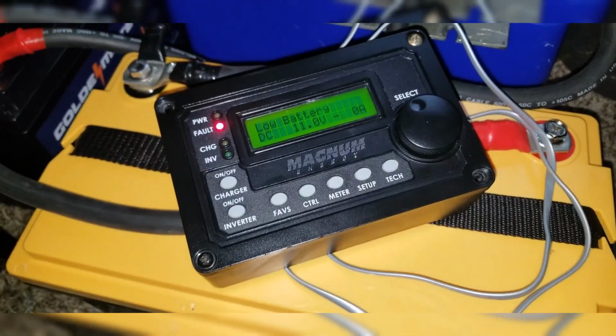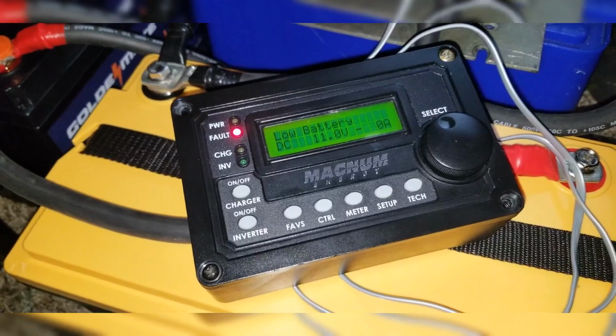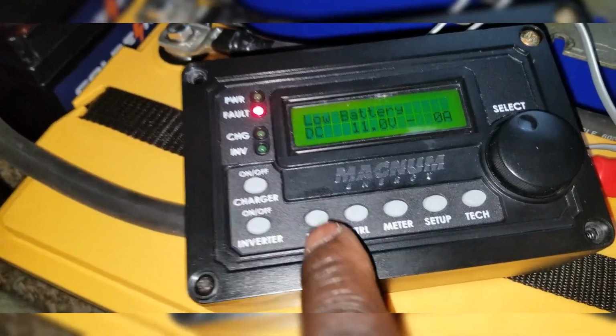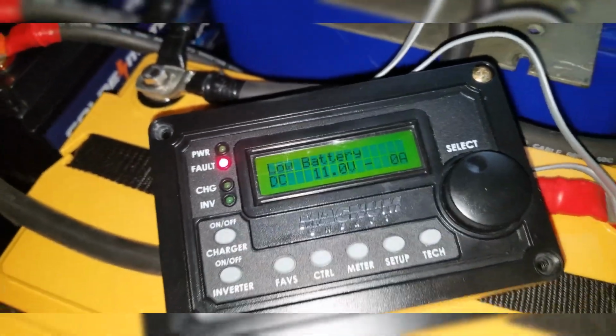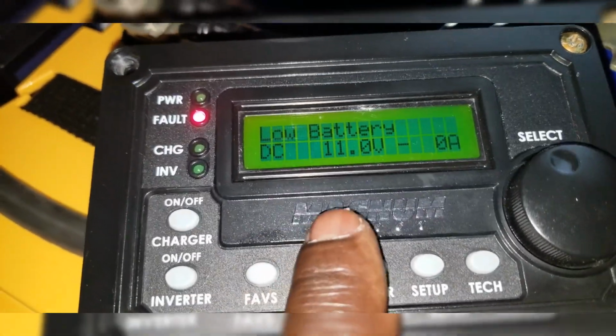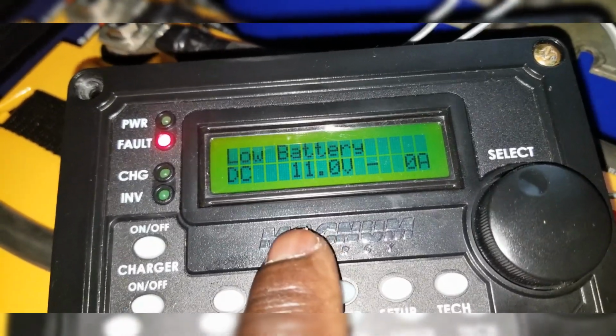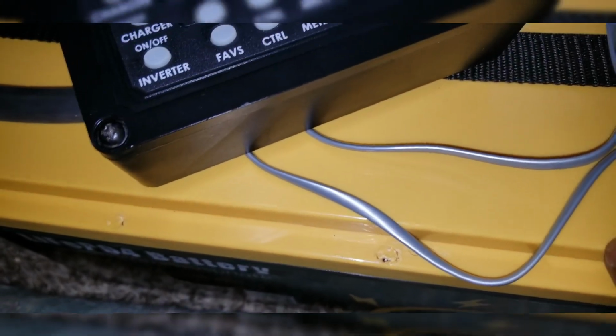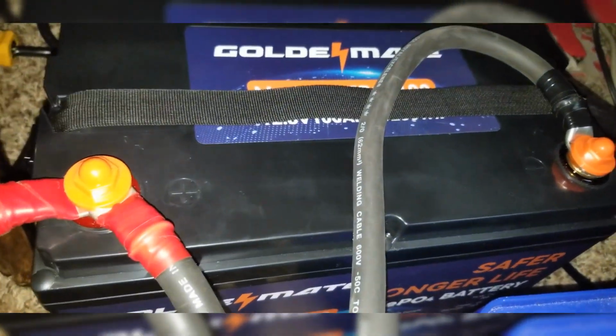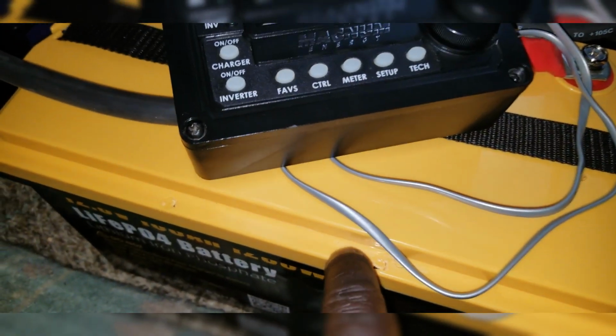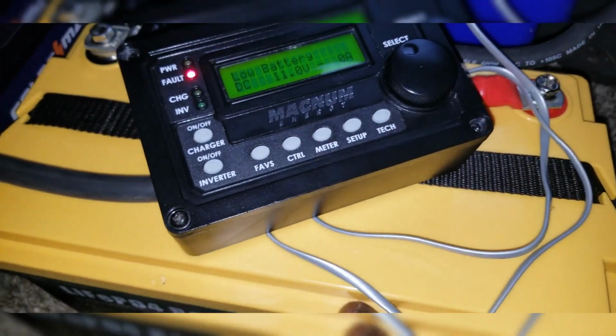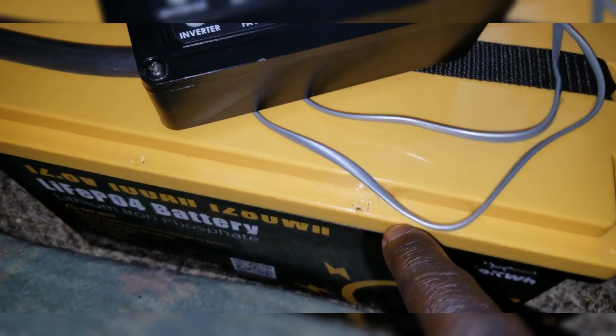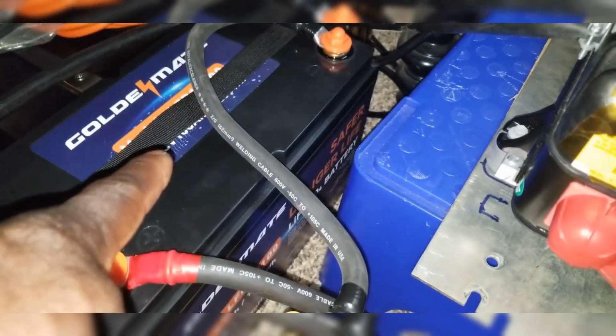I was doing a test on that too. I want to see if the BMS is going to shut down at that low voltage. So maybe I have to go lower than that and see if the BMS is really active. But when it goes down to that, I have to bring it up again. Look at that. Now, this is the other thing I'm about to tell you guys. I was waiting. The voltage is coming back up slowly from 10 point something, because this unit is already shut off. This one can shut off completely when you see that kind of surge, but this one can still handle it. So the reserve capacity, because the BMS of this one already shut down, maybe it just turned back on for some reason, or the juice from these came back to this BMS right here and reactivated this one, and the power is coming from whichever has more reserve.